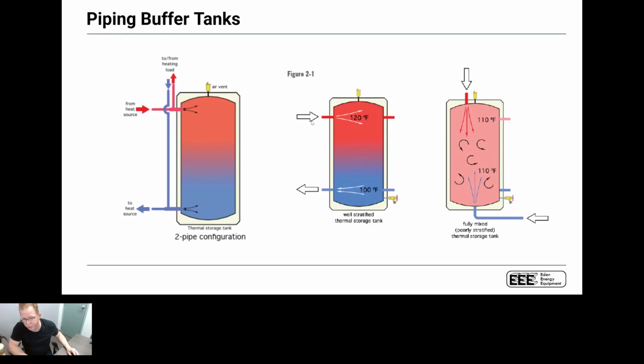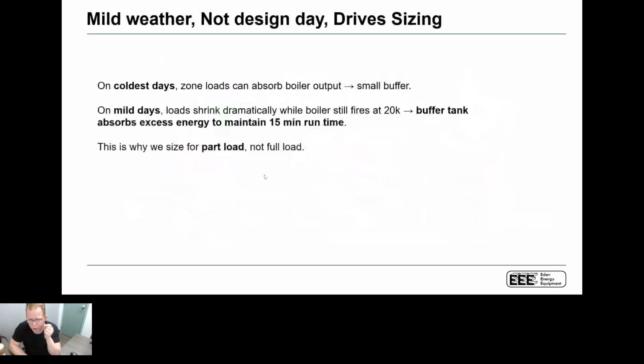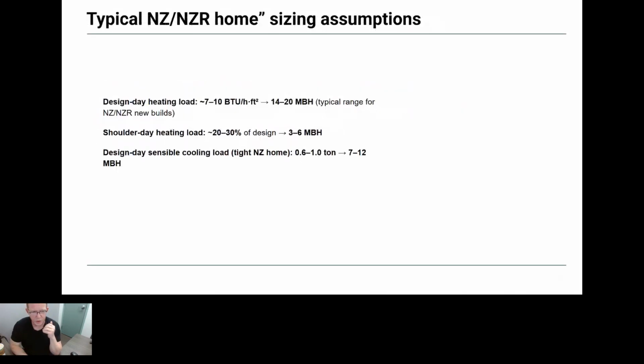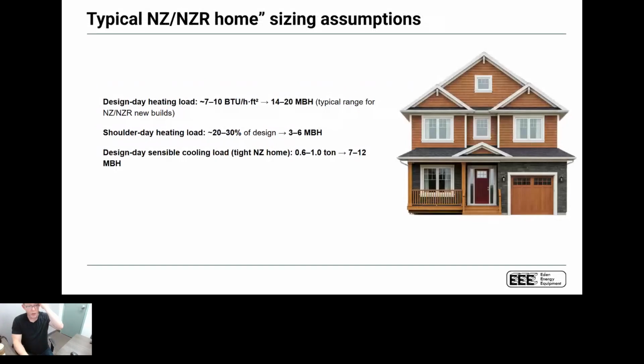Also a fan of this setup. It's also equally good. But where it really shines is when you get into those mild weather days where you've got a 5-ton heat pump, but you don't in fact need the entire load. So let's look at that and understand what that means. A design day heating load, if you look at modern homes that are being built right now, can be anywhere from 7 to 10 BTUs per square foot. Like, it's very, very low. And even if you're looking at 14 to 20 MBH, what happens during the shoulder season where we only have 20 to 30% of design?